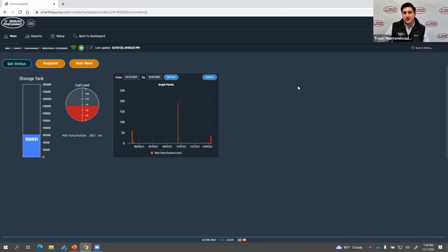I think it has to be an agreement between the end user and the contractor, depending upon what the goals are. If it's being brought from the bottom up, from the contractor to the end user, saying I want to use this to monitor your system and it's part of this package, then that's pretty straightforward. Similarly, top down, if the end user says it's important to us that we have this data logged, and we want you to monitor it, we'll take ownership of it and buy the equipment, which is the model we've seen thus far, but we want you to keep an eye on it for us, then that's a different agreement between the end user and the contractor. Typically we bill the end user an annual recurring subscription for that service, to be able to use the user interface. That typically comes through the end user, but it is possible to also come via the contractor.